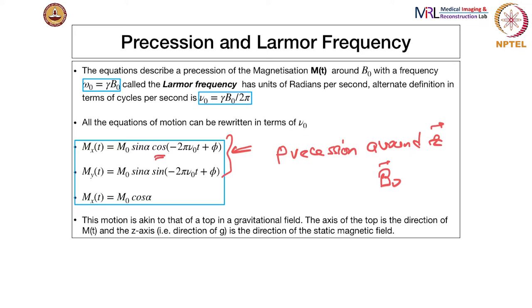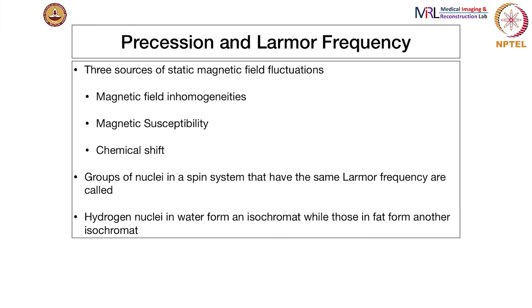The Mx and My components are periodic — this is sinusoidal motion. The Larmor frequency is the gyromagnetic ratio times B0. Now, there are three sources of static magnetic field fluctuations. One is the hardware inhomogeneity itself. The other two are intrinsic properties of the sample: magnetic susceptibility and something called chemical shift. These two affect the value of B0 locally, and this is exploited for imaging.